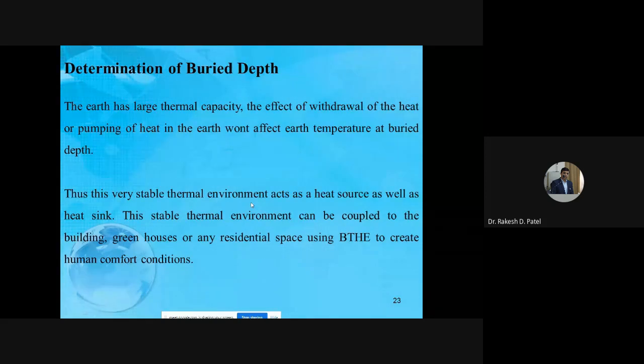Now, the Earth has a large thermal capacity. The effect of withdrawal or pumping of heat in the Earth won't affect the Earth temperature at the buried depth. So this is a very important aspect of the buried depth. This very stable thermal environment acts as a heat source as well as a heat sink. It can be coupled to buildings, greenhouses, or any residential space using this heat exchanger to create human comfort conditions.